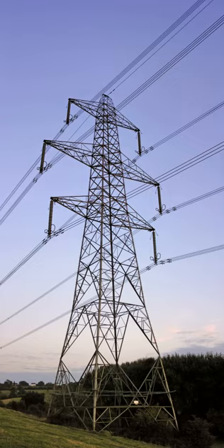Topic: Towers for different types of currents. AC circuits of different frequency and phase count, or AC and DC circuits, may be installed on the same tower. Usually all circuits of such lines have voltages of 50 kV and more. However, there are some lines of this type for lower voltages. For example, towers used by both railway traction power circuits and the general three-phase AC grid.